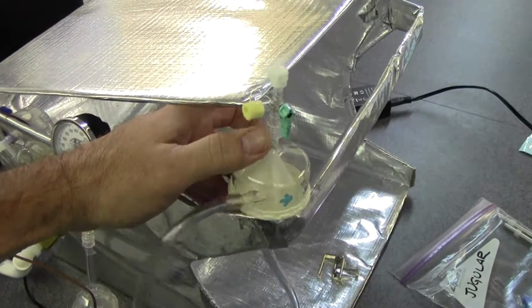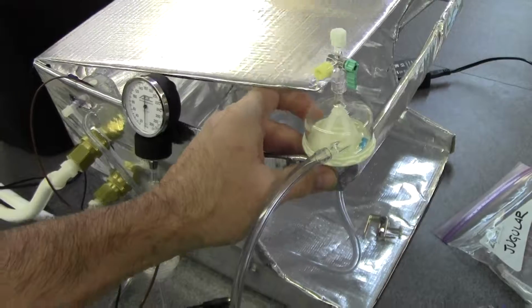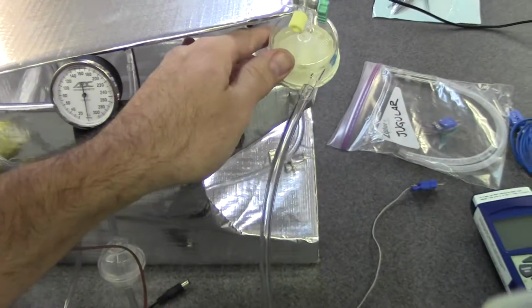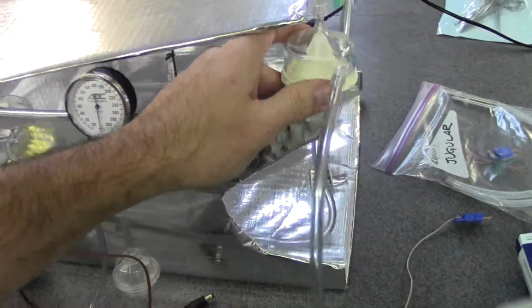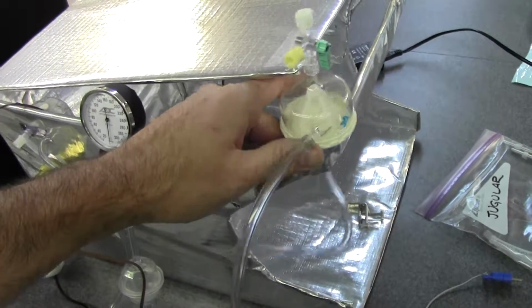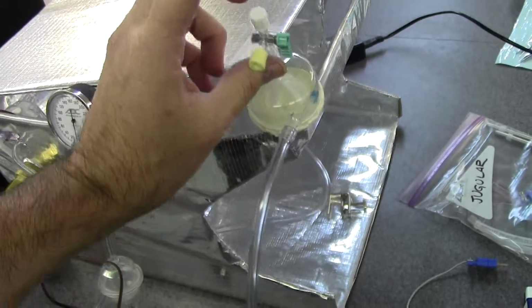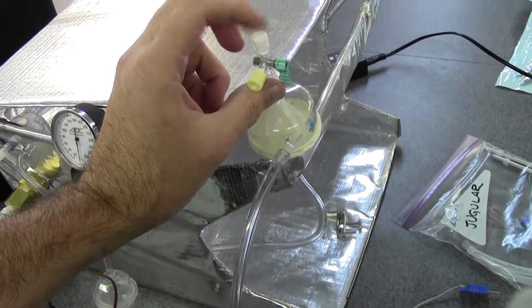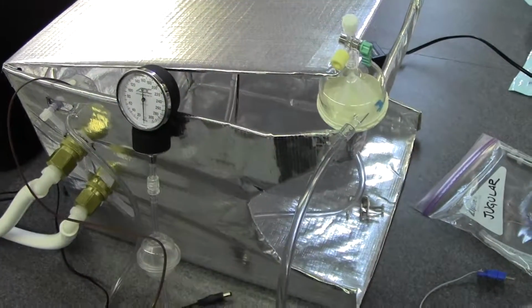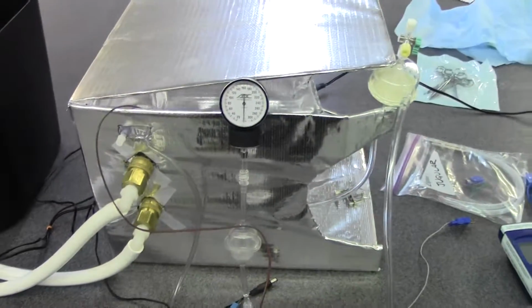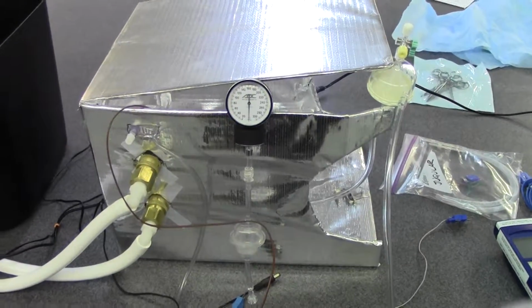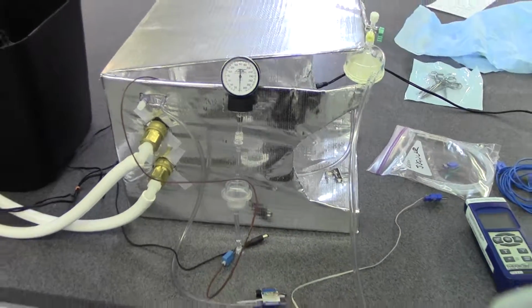Oh, we do have a bubble trap so that if you do happen to get any air into the system when you're swapping out bags, it should get trapped by this. And if this gets too full, you can release a little bit of air through the stopcock right there. You want to run the system between 80 and 100 millimeters of mercury, and that should give you a good result.